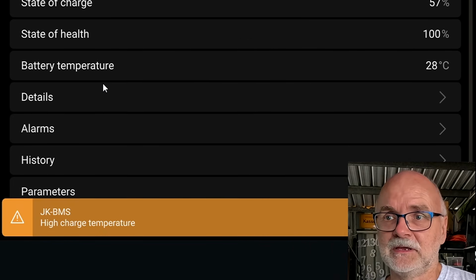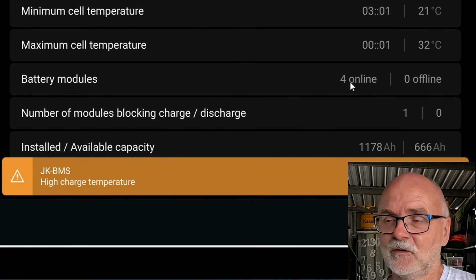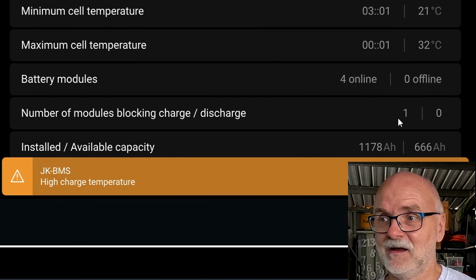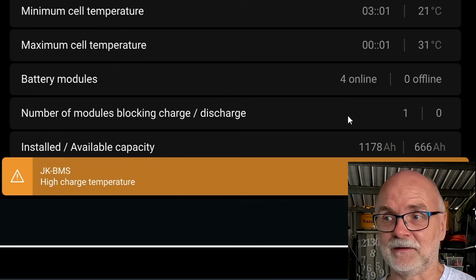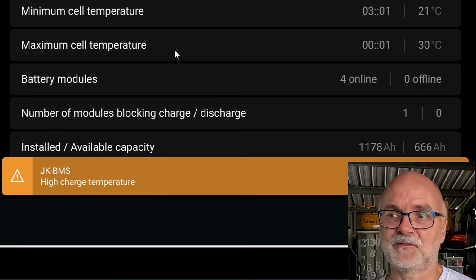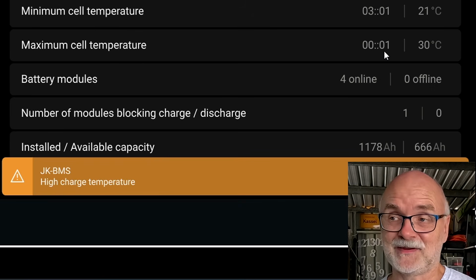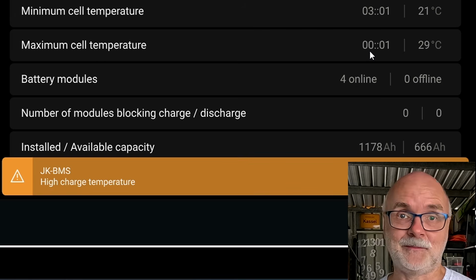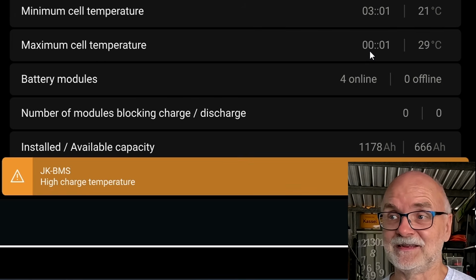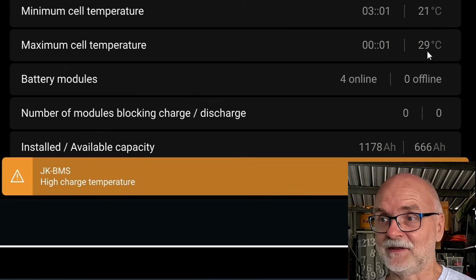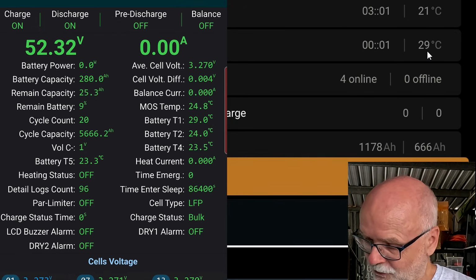And if you have a look here under details, we can see 4 batteries are online, everything is there, but 1 is blocking the charging. Yeah, we can also see here the maximum cell temperature is now our temperature sensor number 1 in the master battery. This is exactly what we have just heated up with Miss Piggy. It is now at 29 degrees, so it should clear actually under 30 degrees.